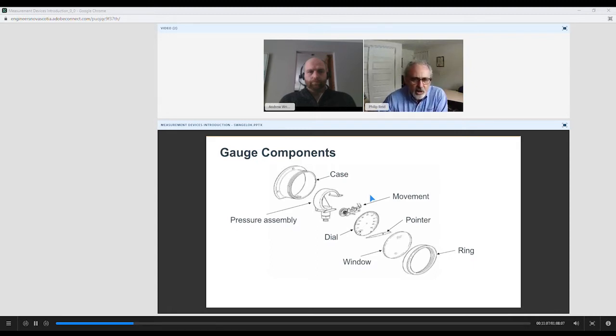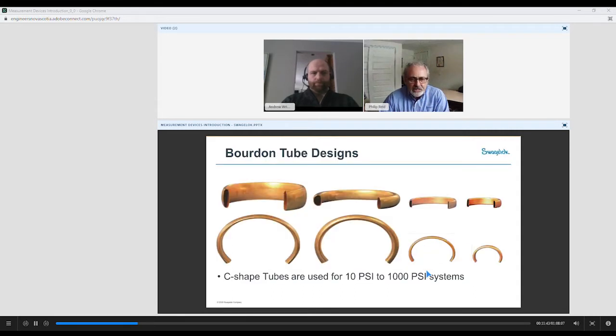Again, ASME B40.100 lays out the case, which contains all of the components. The pressure assembly, this will be the Bourdon tube and the socket and the pressure connection to your media. Inside you have the mechanical movement that I talked about. You have a dial or face, and the pointer, which will indicate the pressure. You will have the window or lens, and then you have a retaining ring, and these can be screwed, bayonet mount, or crimped. There are many different ways, and again, how these are designed and built is laid out in B40.100. So let's go a little bit further.